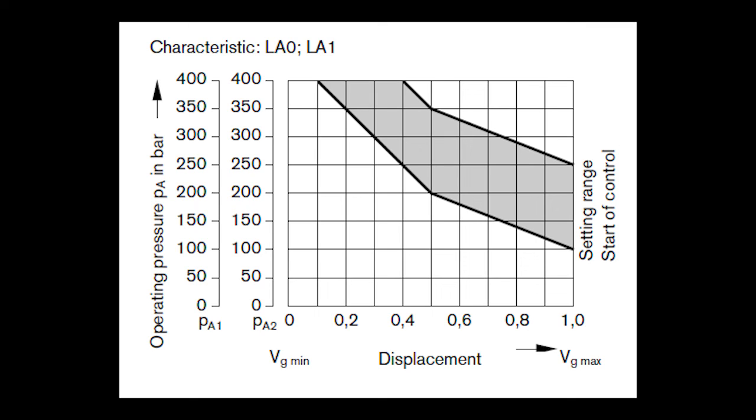If the pilot pressure signal is variably controlled by a load limiting control, the sum of the hydraulic powers is equal to the input power. The pilot pressure for the power override is generated by an external control element or by the mounted pressure reduction valve.